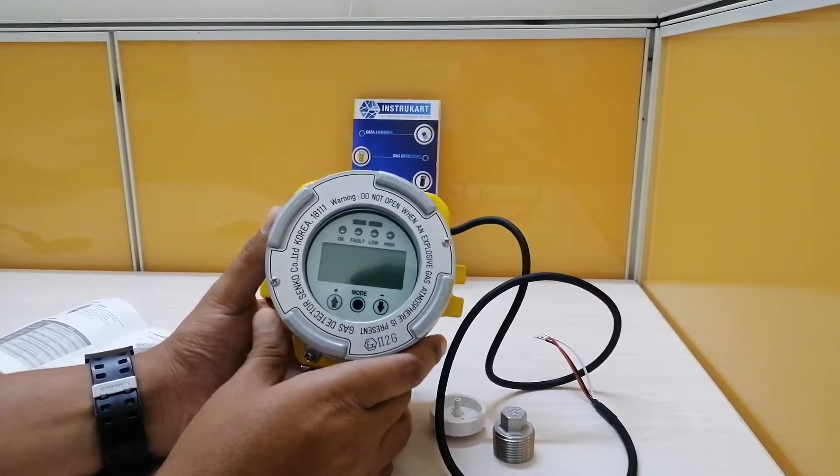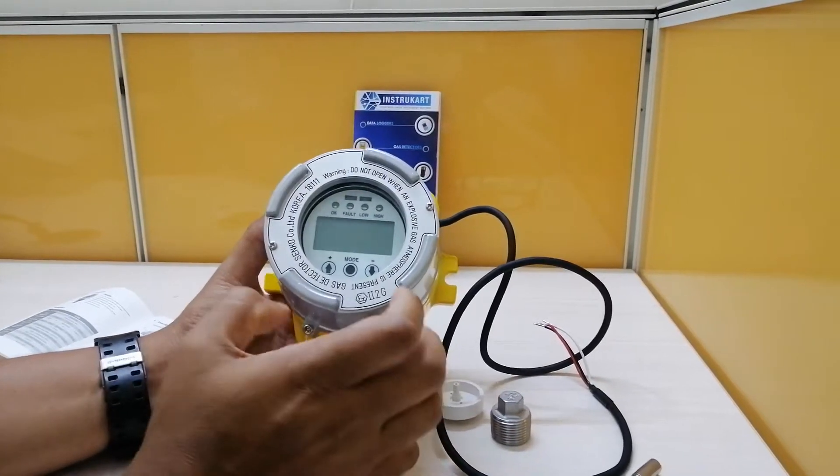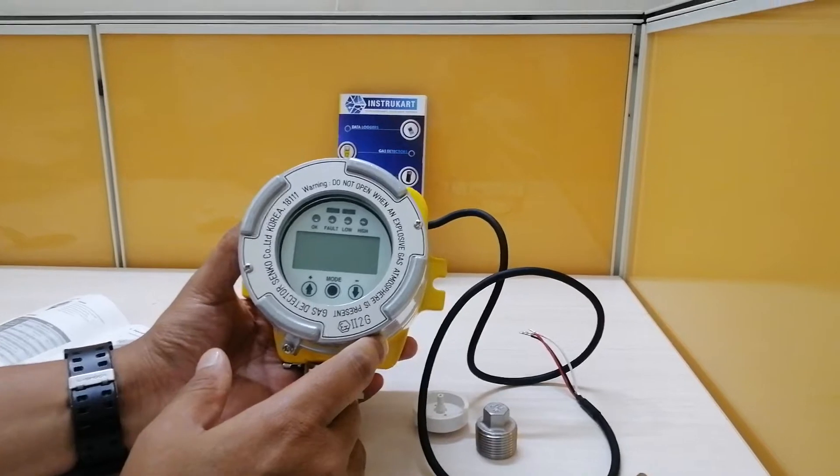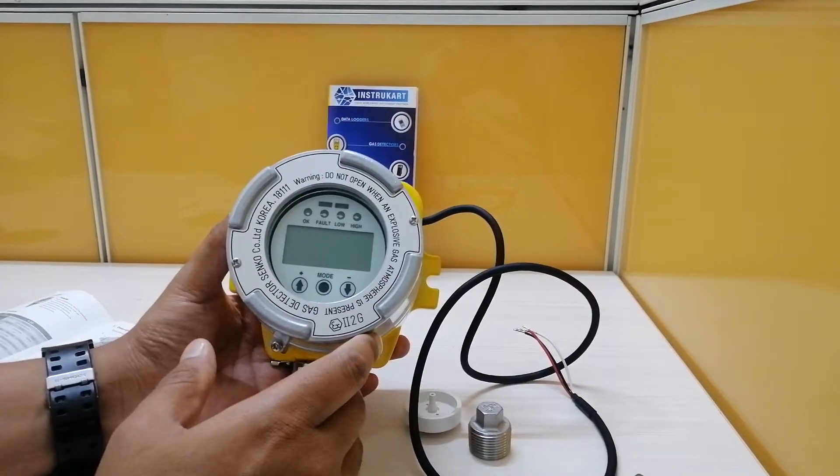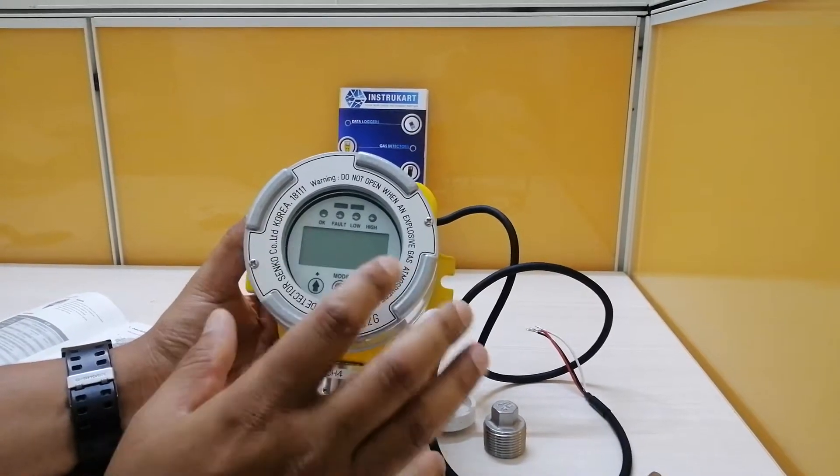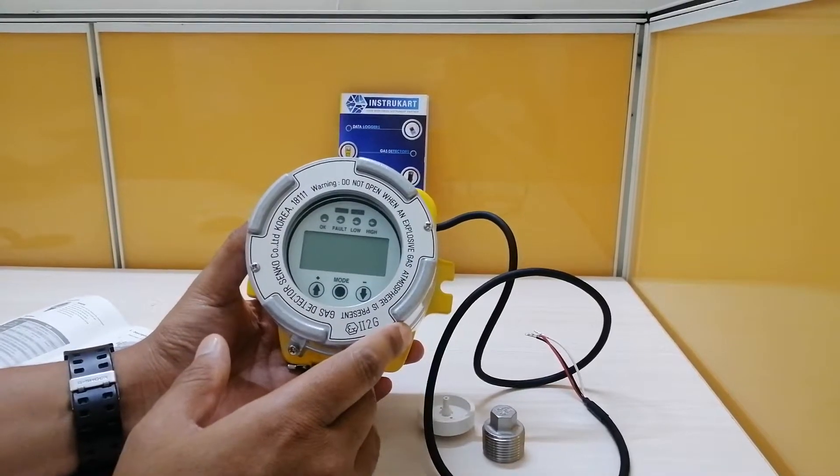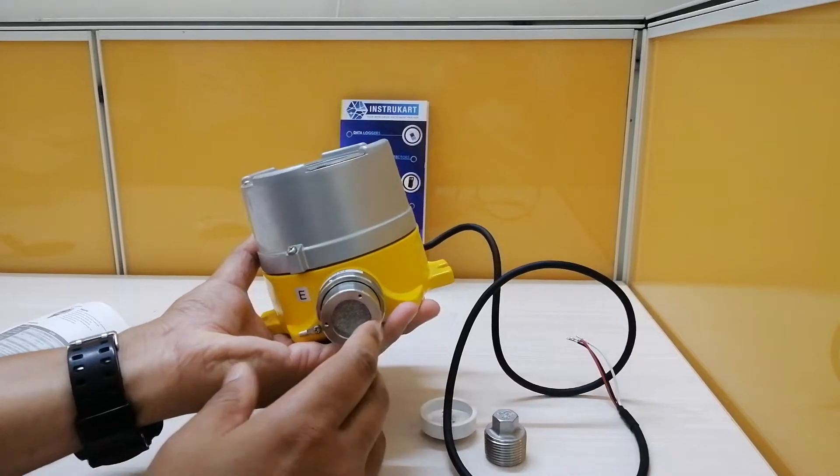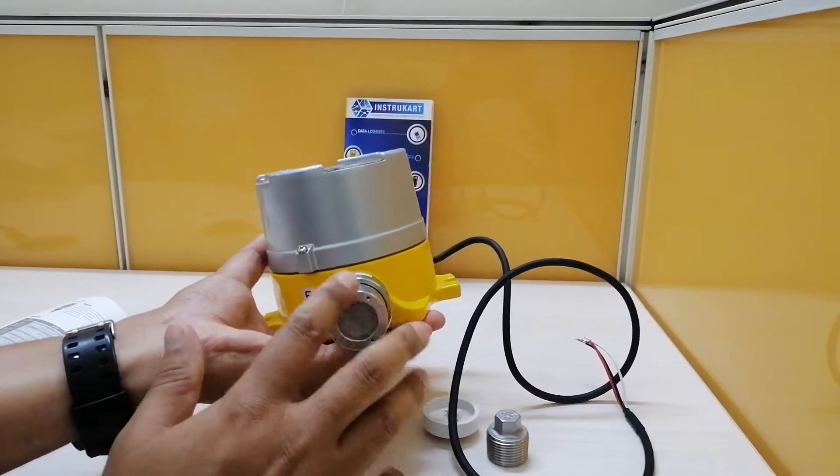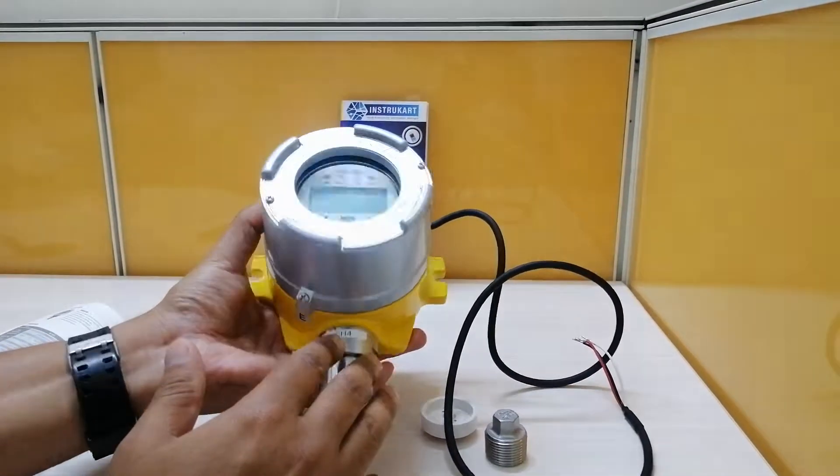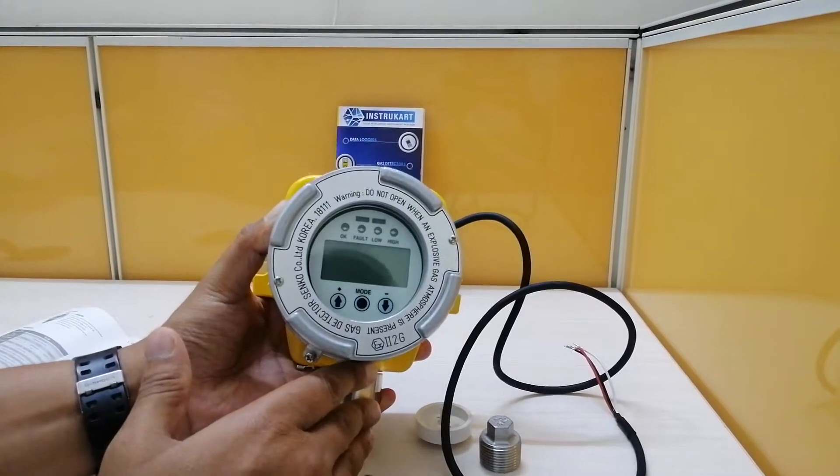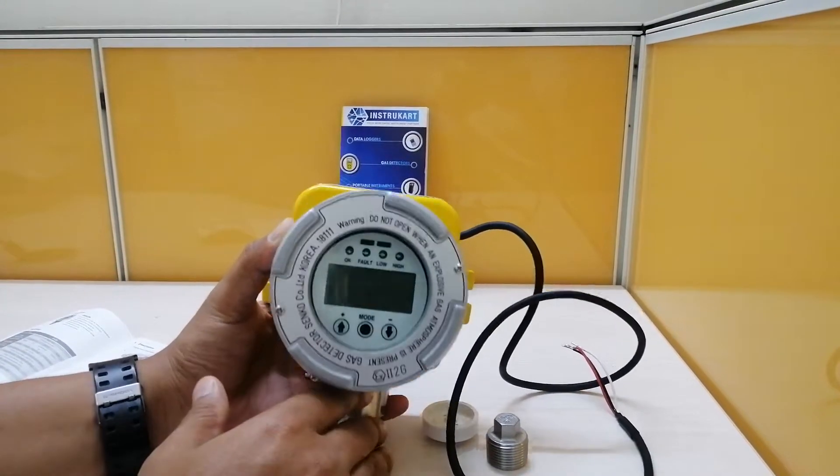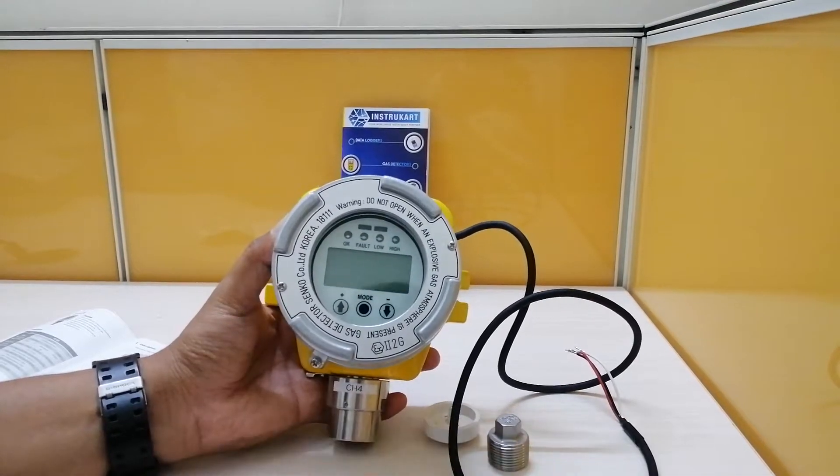This instrument has a model number of SI100. This is an SI100 series from Senko and has both catalytic and IR sensor options with a diffusion type sensor which you can see over here. The measuring range is 0 to 100% LEL and accuracy for this instrument is plus or minus 3% on full scale.